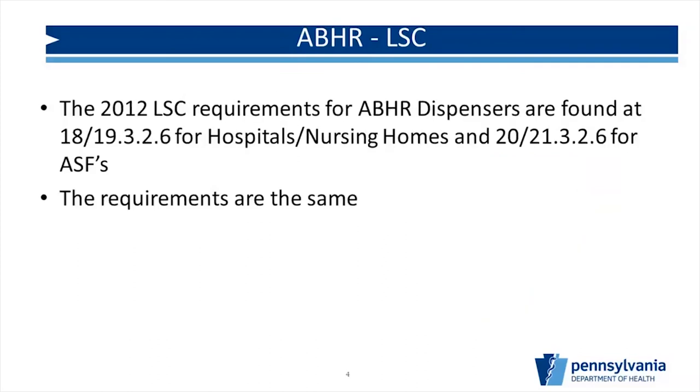When talking about hand sanitizers and hand rubs, the first requirements came out in about April of 2004, so they've been around about 15 years, but there's still a lot of confusion over where you can put them and how to install them — which is why we're addressing this today. The relevant code sections are at 18 or 19, depending on whether you're new or existing, section 3.2.6 for hospitals and nursing homes, and for surgery centers, it's 20 or 21.3.2.6. The requirements are exactly the same whether you go to the hospital chapter or the surgery center chapter.